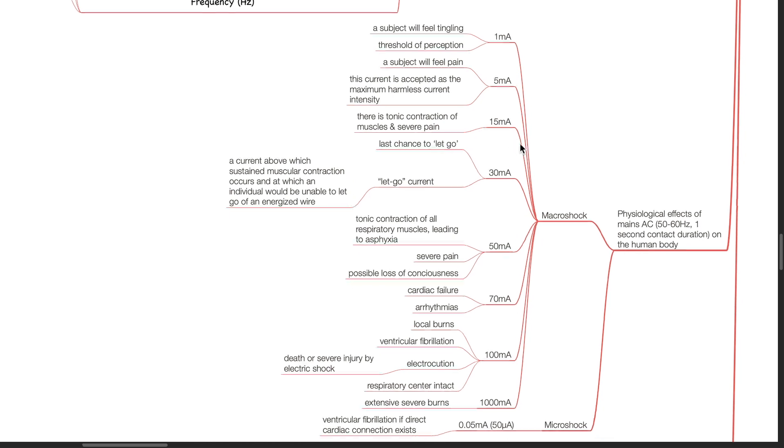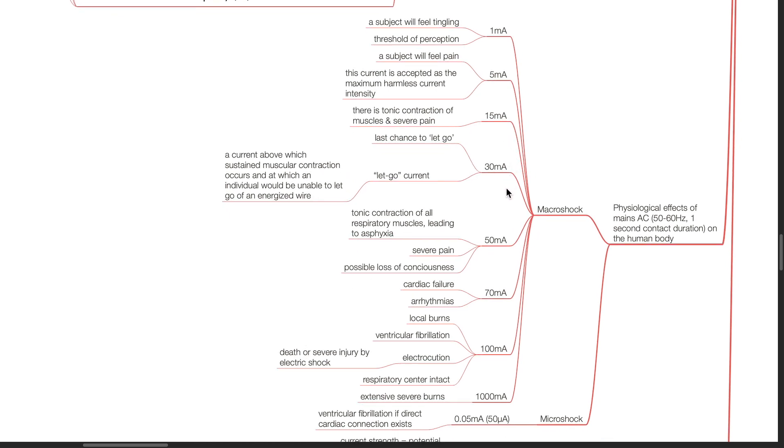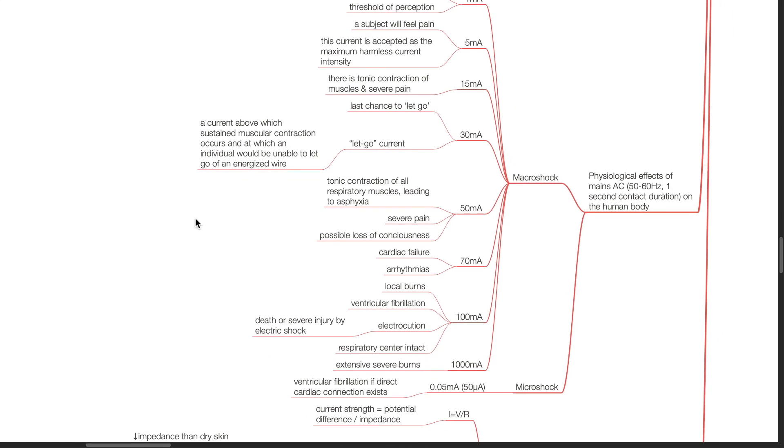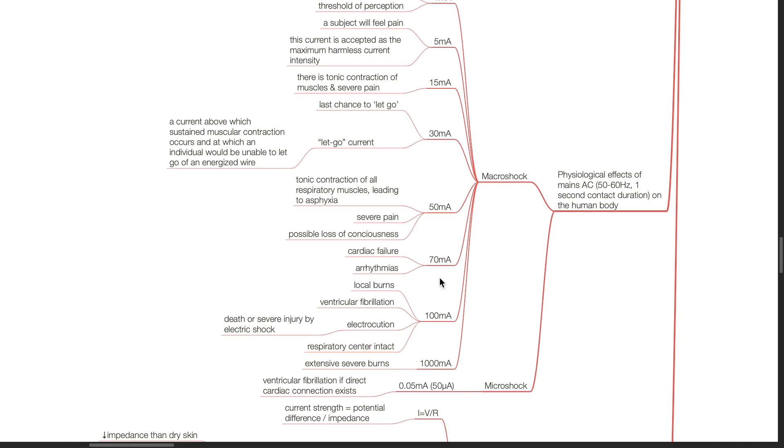At 30 mA, last chance to let go. The let-go current is a current above which sustained muscular contraction occurs and at which an individual will be unable to let go of an energized wire. At 50 mA tonic contraction of all respiratory muscles occur leading to asphyxia. There will be severe pain and possible loss of consciousness. At 70 mA, there will be cardiac failure and arrhythmias. At 100 mA, local burns, ventricular fibrillation and electrocution occurs. Respiratory center remains intact.